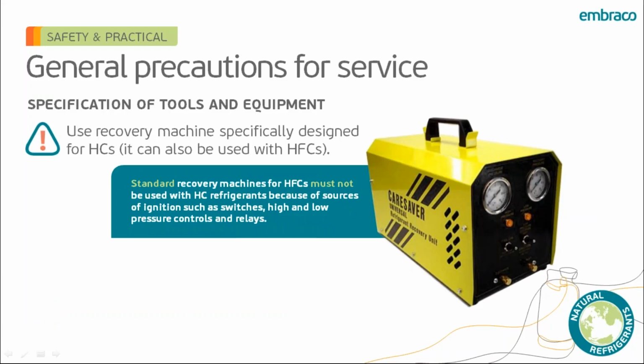So, concerning the reclaim machines, we do need to use a recovery machine that's specifically designed for hydrocarbons. Of course, it can also be used with the older refrigerants, HFCs and HCFCs. We need to do this because the standard recovery machines can't be used because of the sources of ignition such as switches, high and low pressure controls, and relays. So this is something we need to be very careful about.